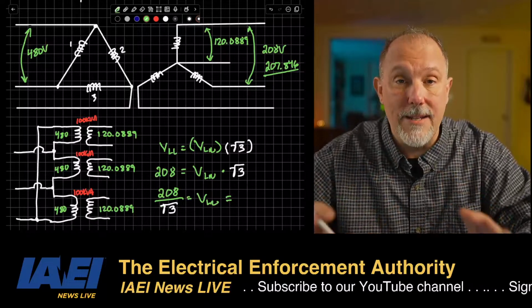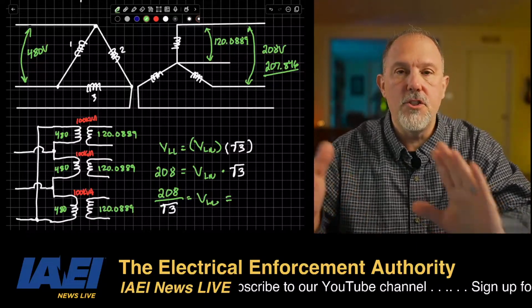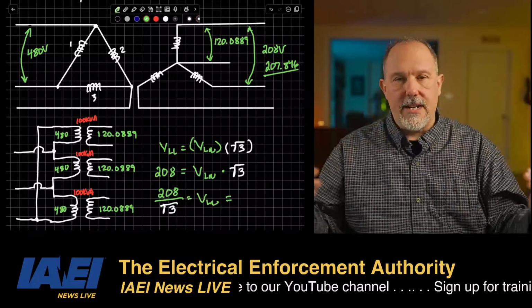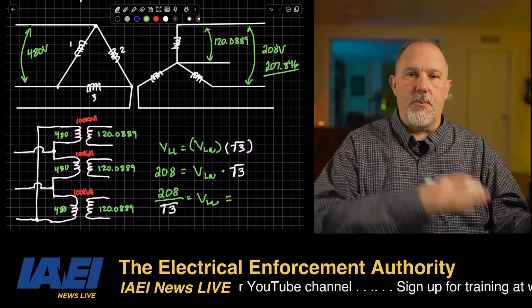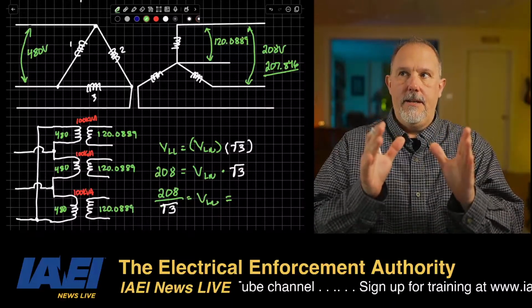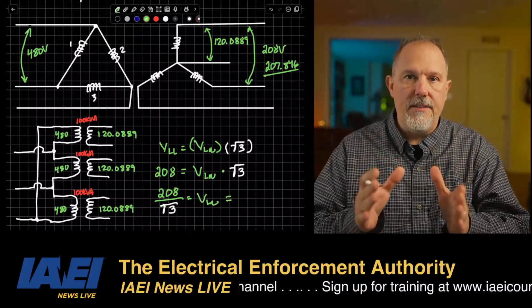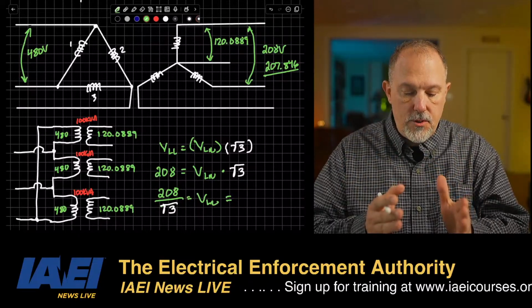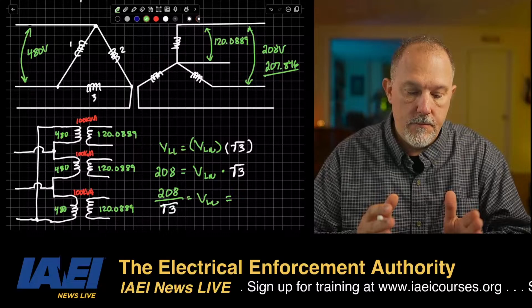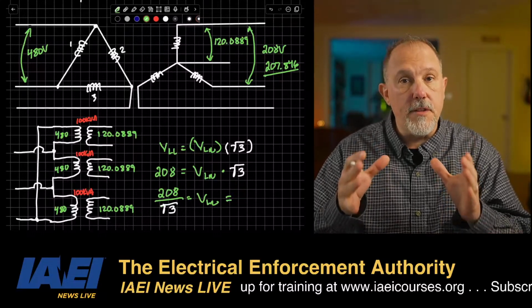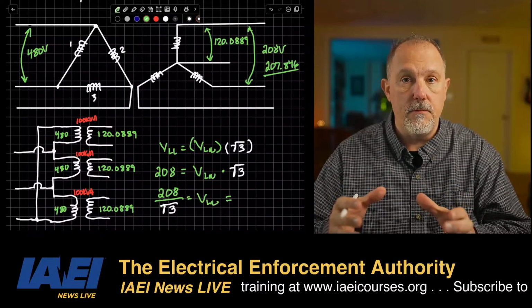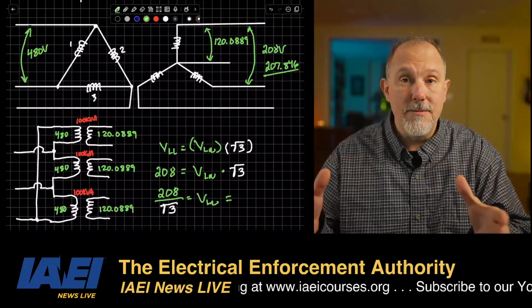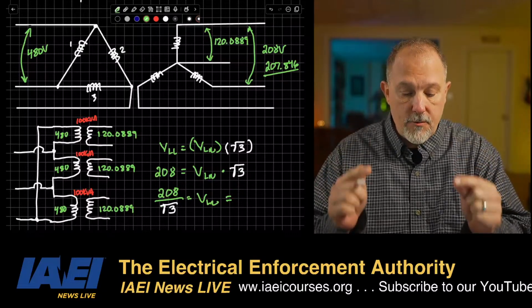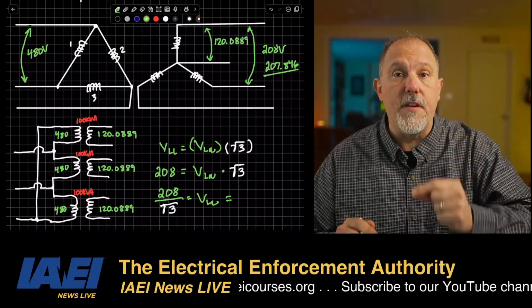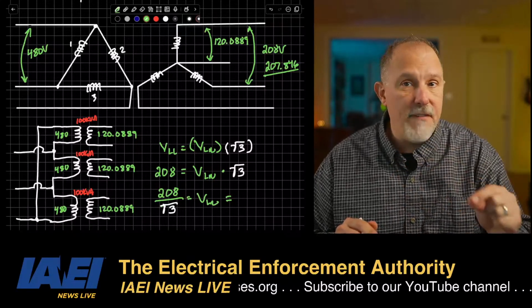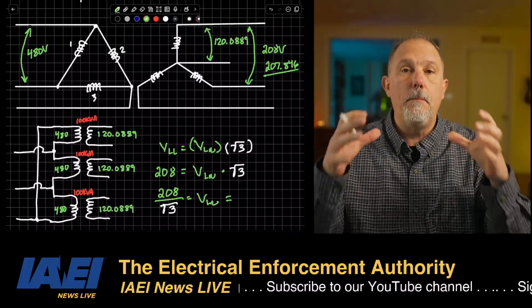And the reason I'm spending time on this, Dawn, is because if you're using primary and secondary voltage to transfer currents from secondary to primary, depending upon how you do this, I've had people tell me I have to use a 4-to-1 ratio. Always, because the turns ratio for this bank of transformers is a 4-to-1 ratio. And my argument is no, it's not. It's a 4-to-1 ratio for each individual single-phase transformer, but it's not a 4-to-1 ratio for the transformer bank.